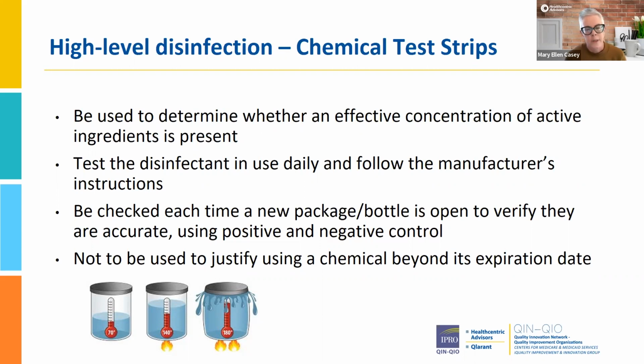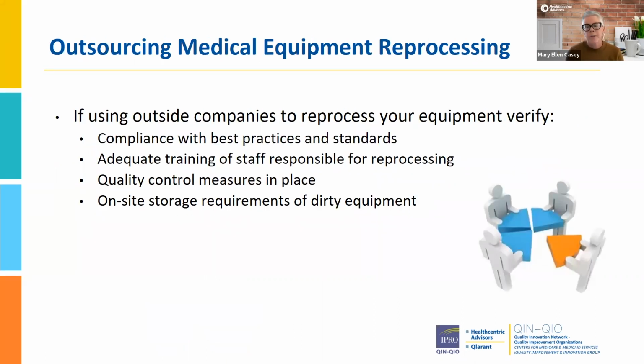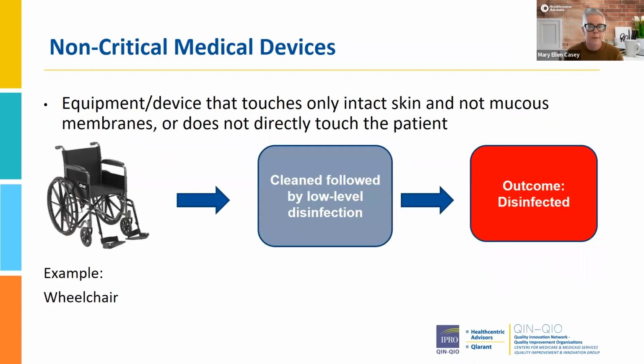You cannot justify using a chemical beyond its expiration date if you take a chemical test strip that's within its user appropriate dates and dunk it in a concentration and say, oh no, it passed the test. If the solution is expired, it doesn't matter. The chemical strips can't be used in it. So it's all those things that are so important to make sure that high-level disinfection is actually working properly. And if you use a third-party external company for reprocessing, these are a lot of the things that you need to keep in mind. You may not be doing this type of reprocessing in your facility, but you want to make sure that your third-party vendor is doing what they need to do to reprocess it properly.